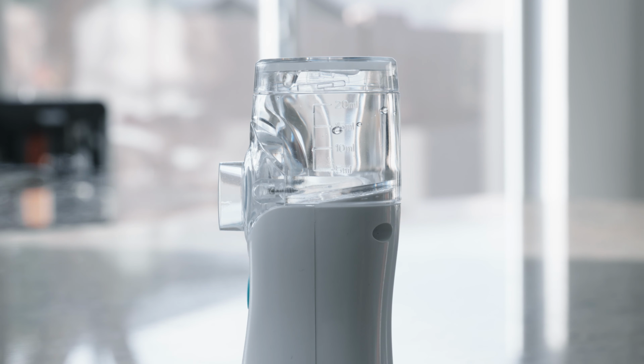Make sure to keep the nebulizer upright while operating. The medicine reservoir has been engineered to deliver all of the medicine when held properly. It is okay to tilt the unit slightly towards the operator. Most medications will only require one timed cycle or less. If there is still medication in the reservoir after one cycle, simply power the nebulizer back on by holding the power button for 3 seconds and selecting your flow rate.